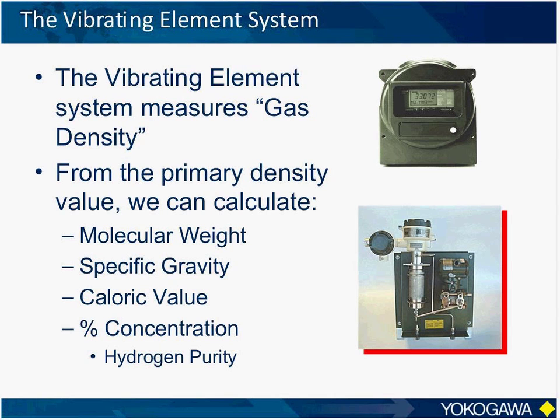Now, the primary measurement of the vibrating element analyzer is gas density, and it's from this primary density value that we are able to calculate a number of secondary values. In any application, basically with any combination of gases, we are able to calculate specific gravity and molecular weight from the density. In certain applications, specifically binary gas streams or pseudo-binary gas streams, we can also calculate a caloric value, or BTU, or an actual percent concentration of a constituent of the gas stream. We will discuss later a specific example of percent concentration applications, which is hydrogen purity in a power generator.